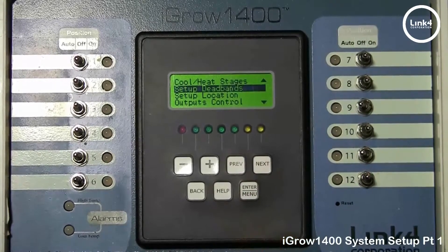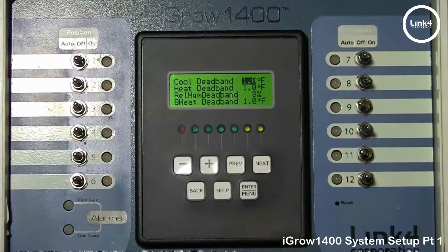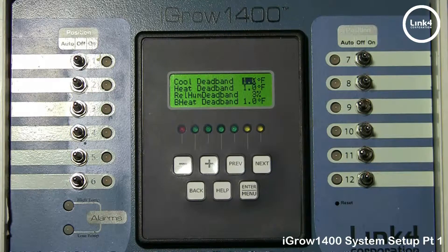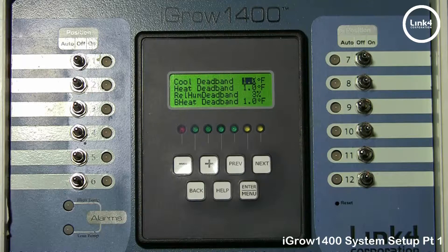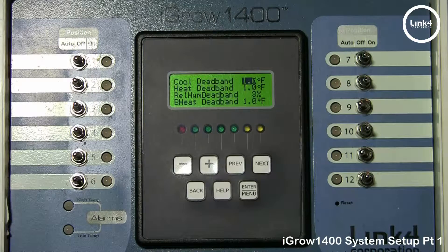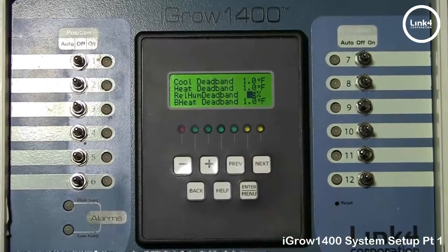The next option is Set Up Dead Bands. Hit Enter Menu to get inside. We have the cool, heat, relative humidity, and bottom heat dead bands. The dead band, or hysteresis band, is the number of degrees the temperature needs to drop from the lower boundary of its current stage before it switches to the lower stage. Dead bands prevent equipment from cycling and stages from changing frequently. A typical dead band might be between one and two degrees, but the dead band must always be smaller than the stage width.